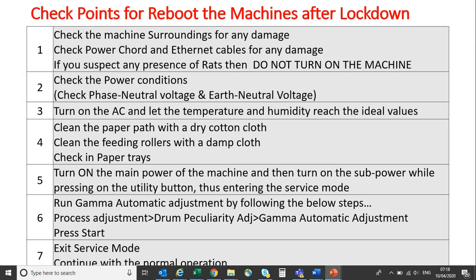After checking the surroundings, check the power conditions. You can take help of your local electrician for this. The main checks are phase to neutral voltage and earth to neutral voltage. Phase to neutral voltage should not be more than 230 volts AC, and earth to neutral voltage should not be more than 2 to 3 volts.